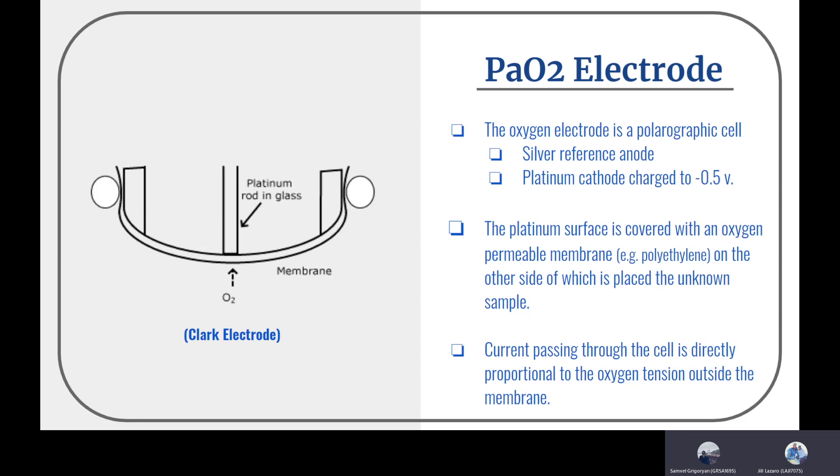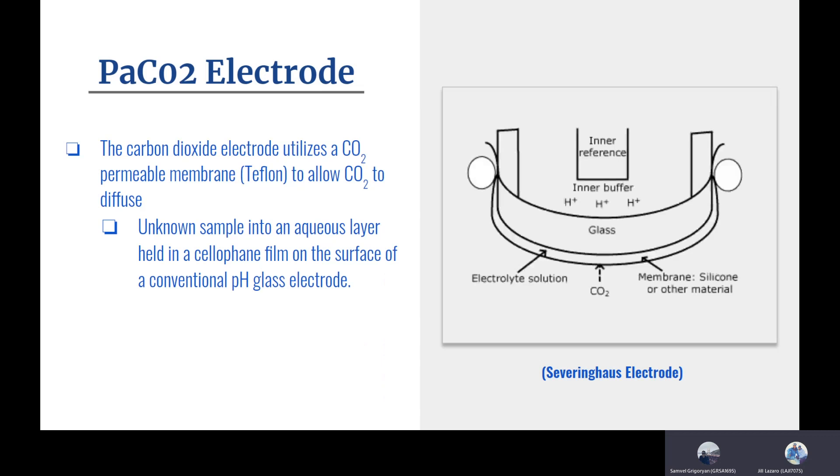The third one is the PaCO2 electrode, the carbon dioxide sensor. The carbon dioxide sensor uses a CO2 permeable membrane, known as Teflon, to allow carbon dioxide to diffuse through. As you can see in the picture, the sample passes through the liquid layer on the Teflon, and the sensor measures how much CO2 is able to get through the membrane. This is known as the Severinghaus electrode.